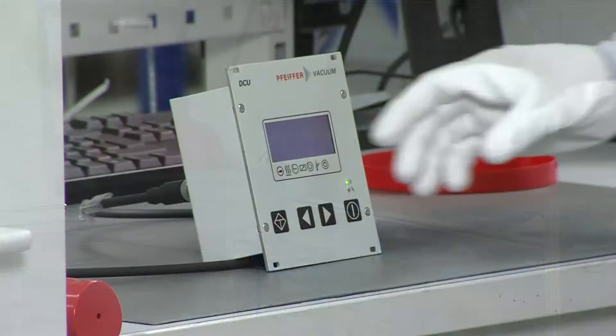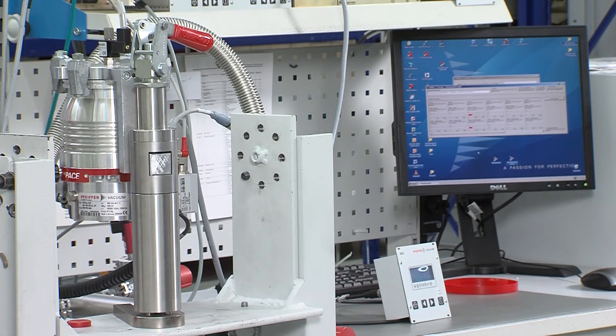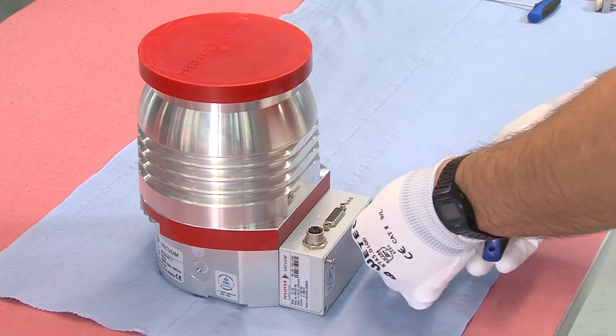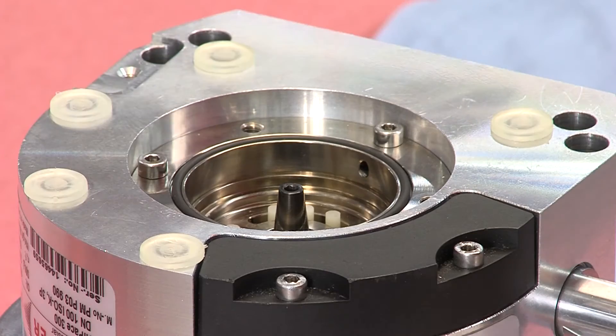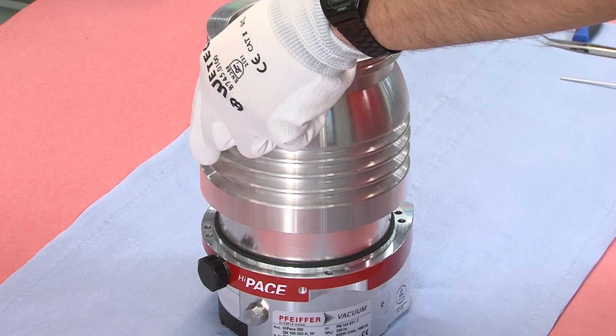In the process, he finds that although the HiPace 300 is still able to operate, it doesn't meet the incoming inspection criteria. Testing shows that there is a problem with the bearing. To deal with this problem, the pump must be dismantled and cleaned. The technician takes the pump apart and prepares it for the cleaning procedure. While doing so, he looks out for any other damage to the various components and makes a note of any findings in the service report.